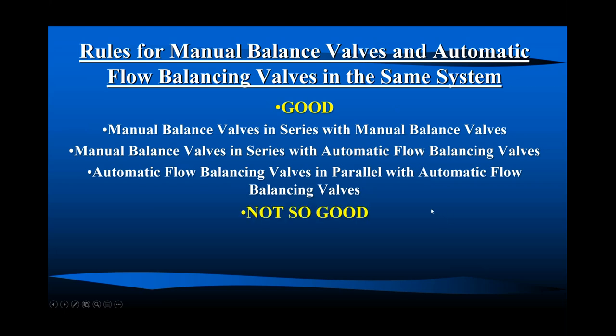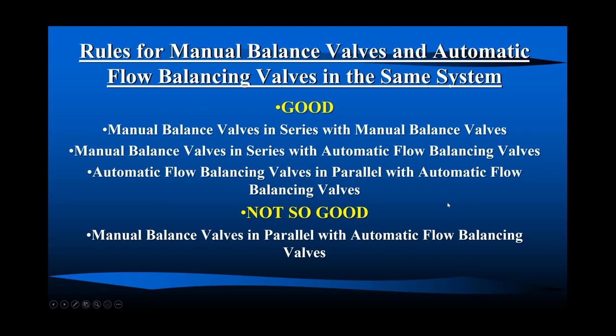Not so good rules: manual balance valves in parallel with automatic flow balancing valves. Nope, can't do that. One has a spring pushing back. One has a fixed orifice, which you can get any flow you want through with enough pressure. So we do not put manual balance valves in parallel with automatic flow balancing valves.